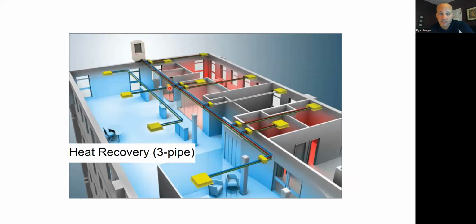So each one of these guys, if you can see, there's a little box added on here. Three pipes come in, two pipes go out. So this box, the zone with the fan and the expansion device, talks to this switching box. And he says, hey, dude, I want cooling. These guys are on cooling over, I want cooling. This guy switches to the cooling pipe. Well, this guy says, I want heating. He has his box switched to the heating pipe. And this guy is able to run both simultaneously. And I'll explain that in a little bit as well.